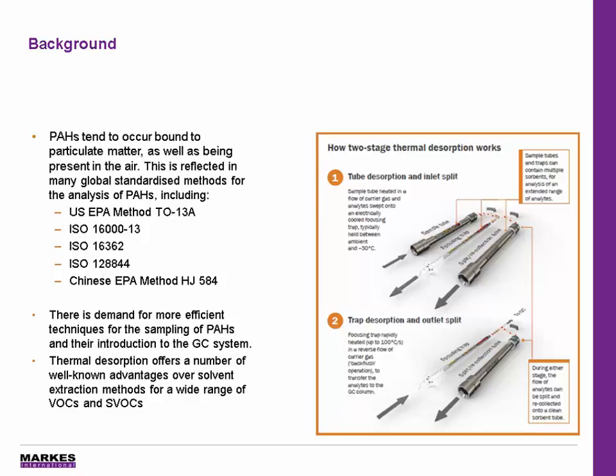Thermal desorption offers a number of well-known advantages over solvent extraction for a wide range of VOCs and SVOCs. The major advantage is the great improvement in sensitivity due to the avoidance of dilution, the high extraction efficiency, and the efficient transfer and injection to the GC. This sensitivity advantage means that the thousand-plus litre sample volumes and large sampling flows traditionally required can be substantially reduced, simplifying the sampling process. Thermal desorption also interfaces with the same type of GCMS instrumentation widely used for standard VOC monitoring, such as benzene in ambient air.